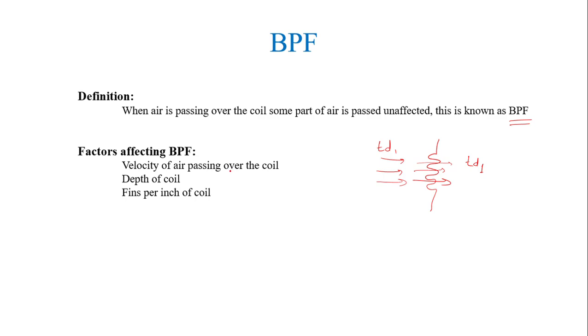There are various factors or reasons behind this loss — the velocity of air, depth of coil, and fins per inch of the coil. First, the velocity of air: when the velocity of air passing over the cooling coil is more, the bypass factor will be more, because when the velocity is higher, the air will be in contact with the coil for less time, and hence the bypass factor will be more.